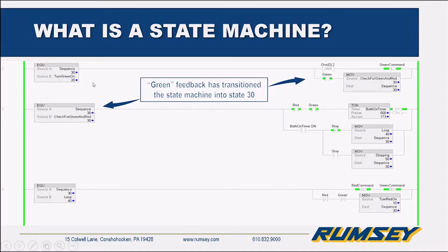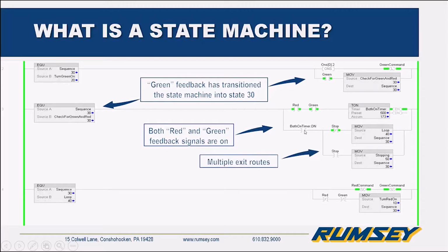Now, here is a more appropriate example where the things match. The green feedback has transitioned the state machine. We have an equal statement that we turned on the green command. We got the green feedback. Move to the next state. The next state happens to be check for green and red. Okay, we match. What's going on in this particular line of code? We can see we have both the red and green feedback, but we're waiting for the timer to time out. The point being, that's what's holding us up and then allowing us to move into the next state.